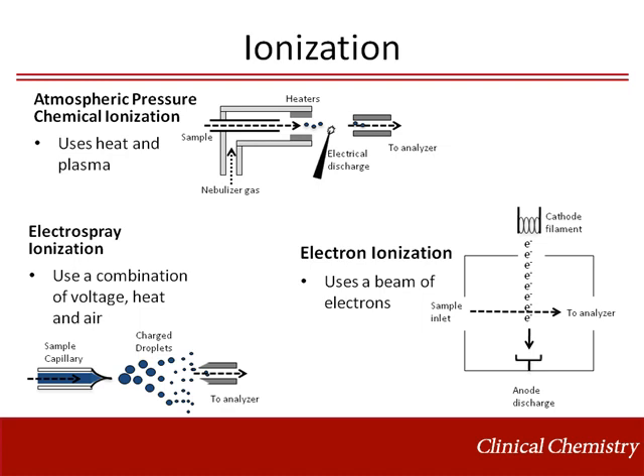ESI sources use a combination of voltage, heat, and air to produce progressively smaller droplets from the liquid sample. As the drops become smaller, ion concentration increases until ions at the surface are ejected into the gas phase. For larger ions such as proteins, the ions are liberated only after complete evaporation of the solvent.